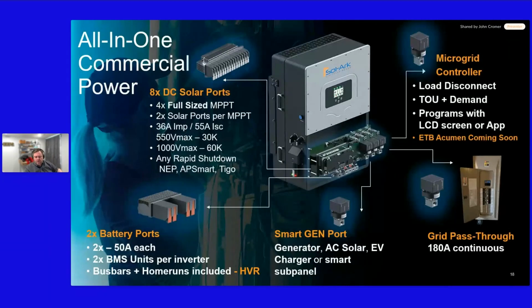You can tie a larger inverter and ignore that 20% rule for load side connections because it's a listed power control system. What most of our installers do is locate the inverter between the meter and the service panel and utilize the inverter's full grid pass through. It passes through 180 amps continuous per inverter, which is enough for most residential homes, especially given that the inverter contributes its own power as well.